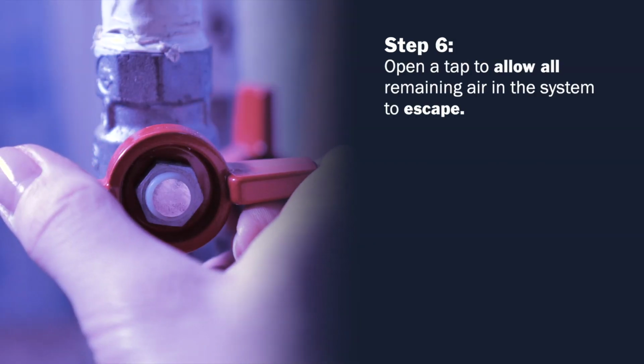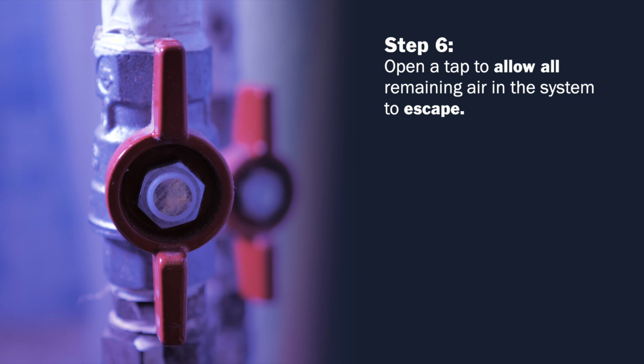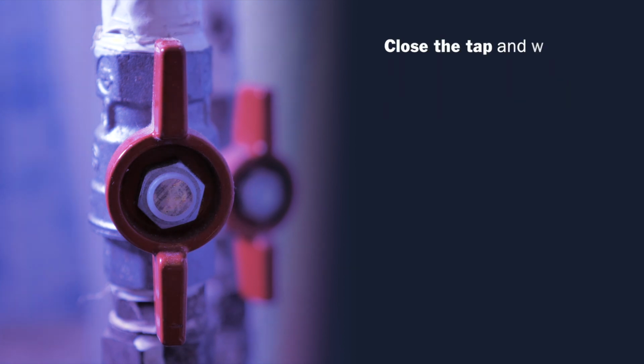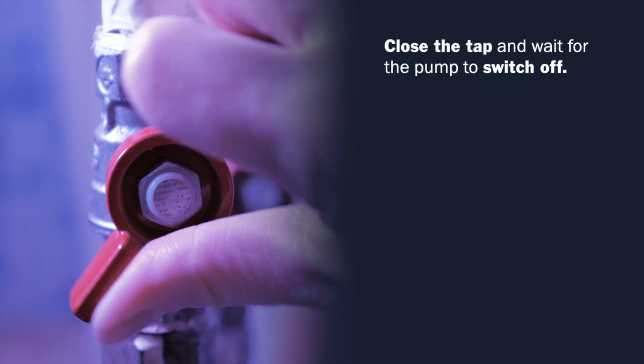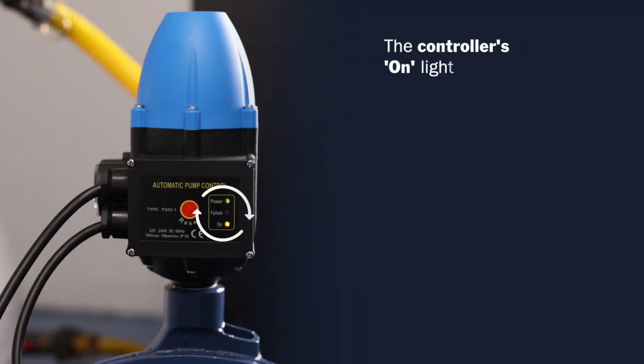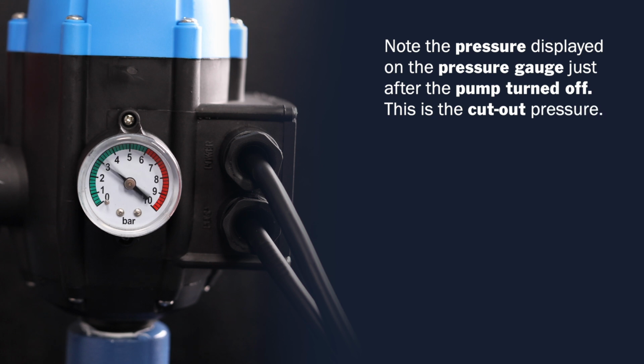Step 6. Open a tap to allow all remaining air in the system to escape. Close the tap and wait for the pump to switch off. The controller's on light will turn off. Note the pressure displayed on the pressure gauge just after the pump turned off. This is the cutout pressure.